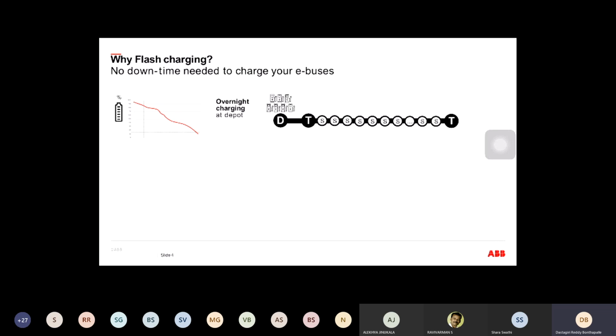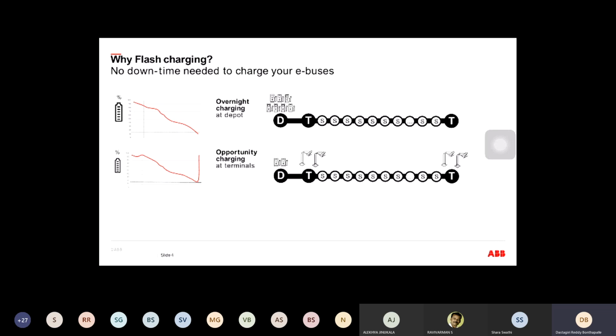Let's see how deep the discharge happens in the three different technologies. In overnight charging, you charge at only one instant. Let's say you start at 100% SOC, then finally at the end of the day you reach 10% or 15%. So the depth of discharge is around 85% or 90%. The more the depth of discharge, the lesser the battery life. Take any chemistry of the battery, this is valid.